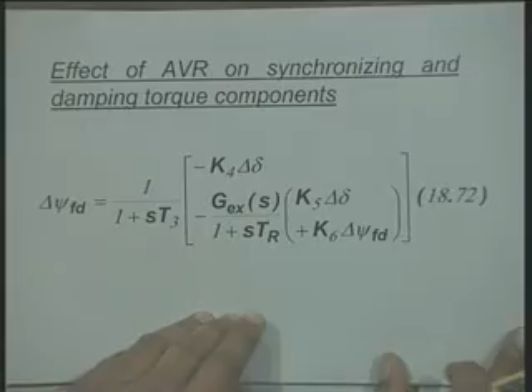This is exactly similar to what we did actually when we assumed the delta Efd equal to 0, right. But since now we are including the exciter or excitation system, the expression for delta psi fd becomes slightly more complicated. Okay. But here this delta psi fd which we are writing down here, right, is now a function of these constants. You can see all the constants which are coming in this picture except K1. You have K3, K4, K5, K6, right. K2 does not come in the picture so far as this delta psi fd is concerned, right. This is a function of these 4 parameters, it is a function of the transfer function of the exciter, and is also a function of these constants like Tr and so on.